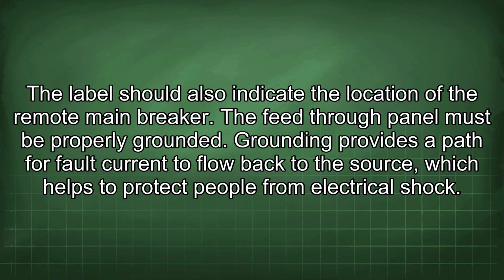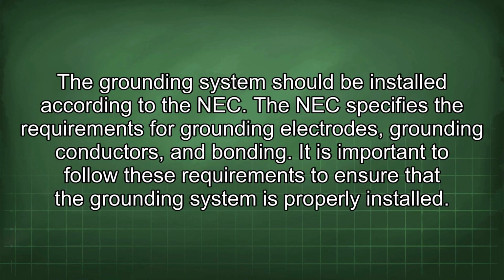The feed-through panel must be properly grounded. Grounding provides a path for fault current to flow back to the source, which helps to protect people from electrical shock. The grounding system should be installed according to the NEC. The NEC specifies the requirements for grounding electrodes, grounding conductors, and bonding. It is important to follow these requirements to ensure that the grounding system is properly installed.